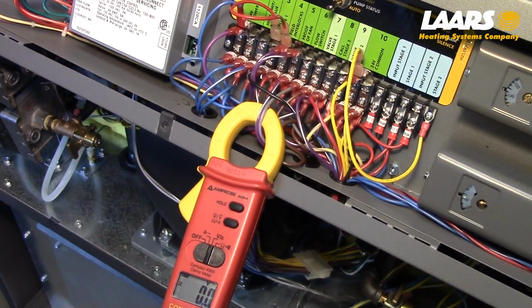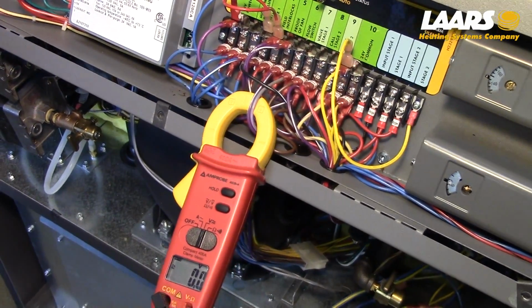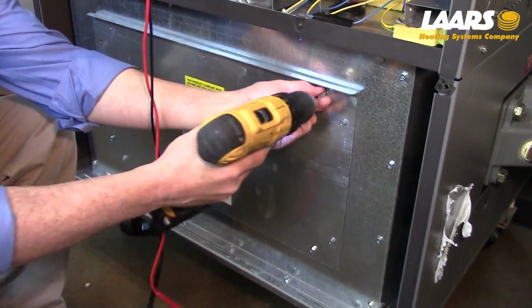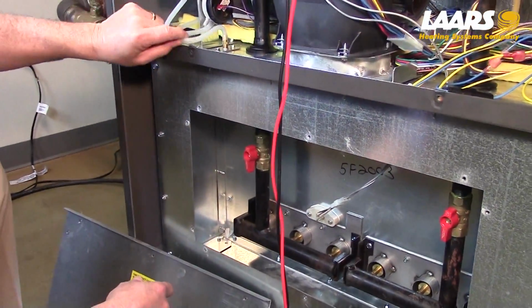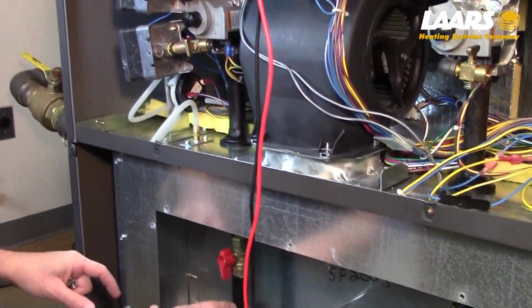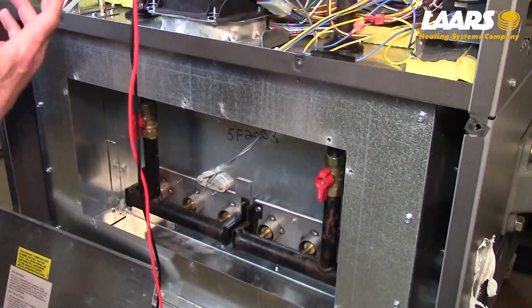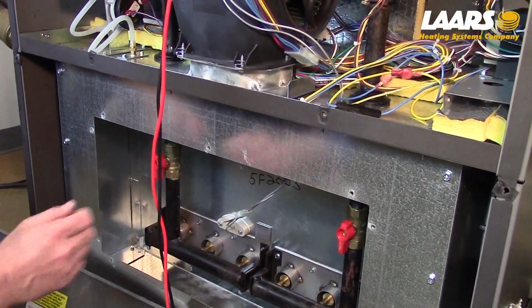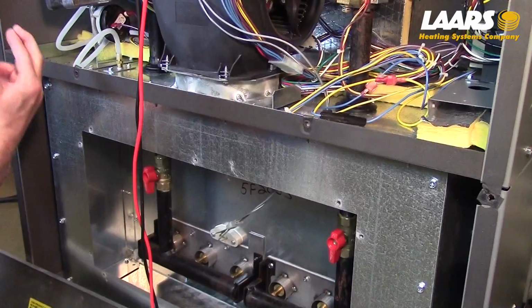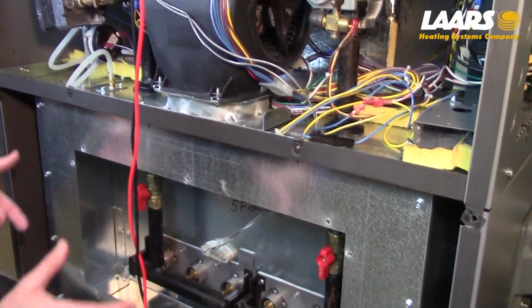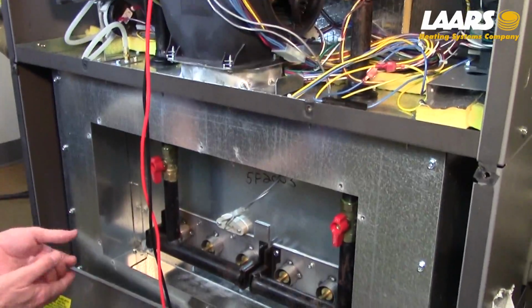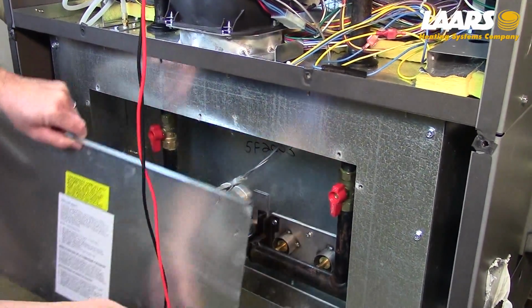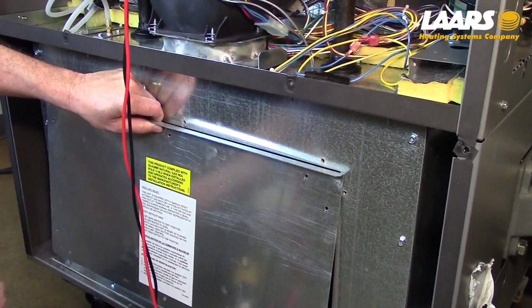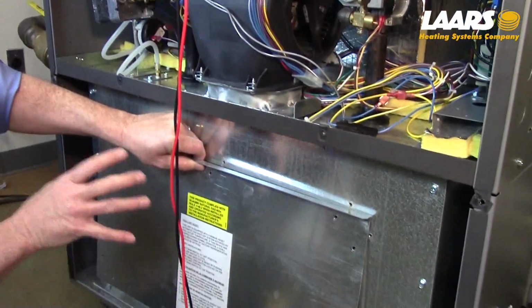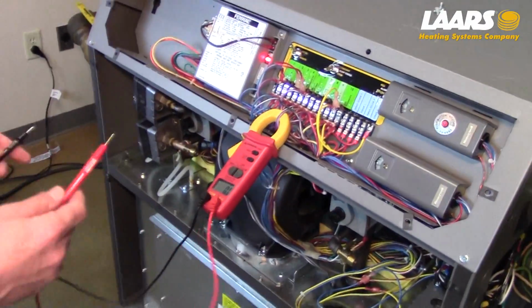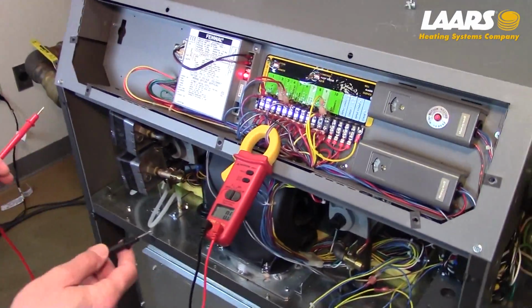I do want to mention to you, if you don't have it there, okay, you need to check your blower. Now a lot of times if your air pressure switch, which is right here, is not made, people have replaced igniters, and then they want to test the boiler. This cover has to be on, or all of your air pressure is coming out here, and therefore your pressure switch won't make. Also, when putting it back on, put all of the screws back in, because if I only put 2 screws in, I've got air gappage on the bottom, and all that air pressure is going to come out, and it will not make the pressure switch. So make sure this is back on tight. Okay, so again, we've then checked the proof of fan.